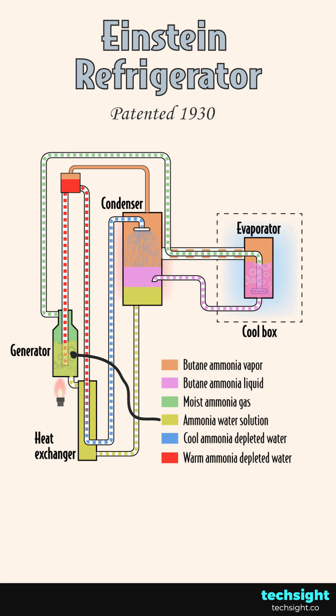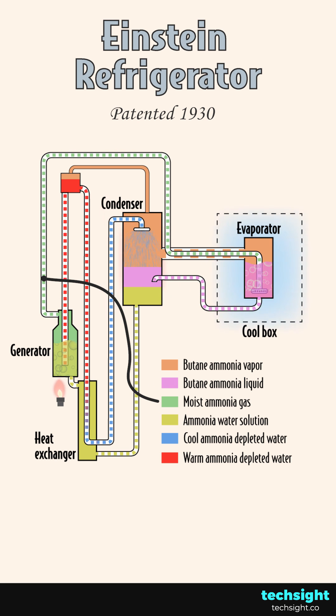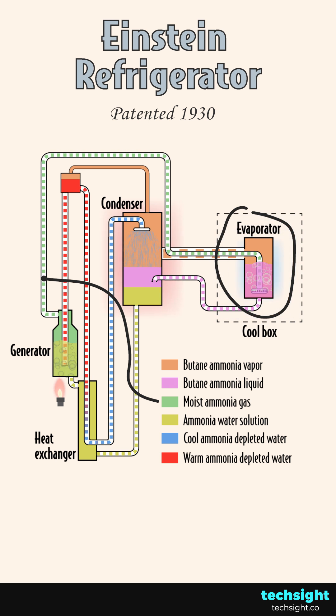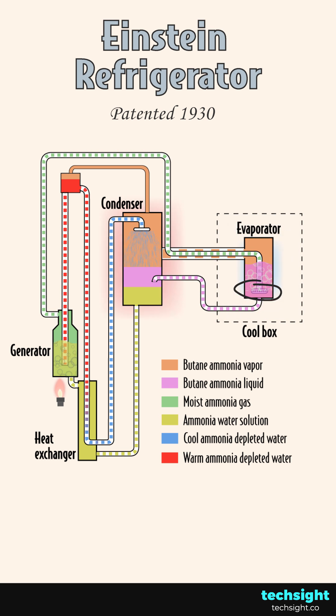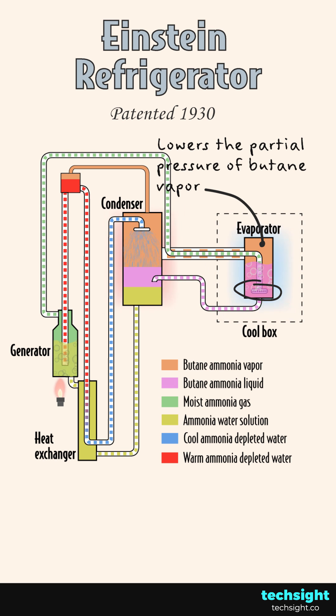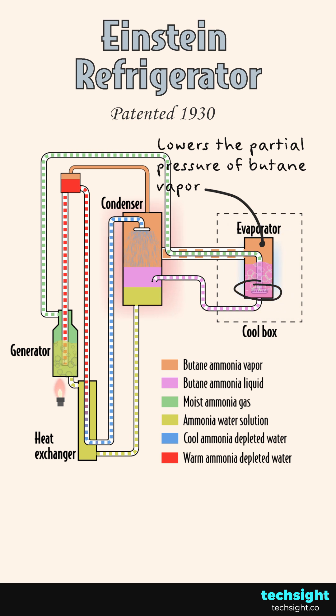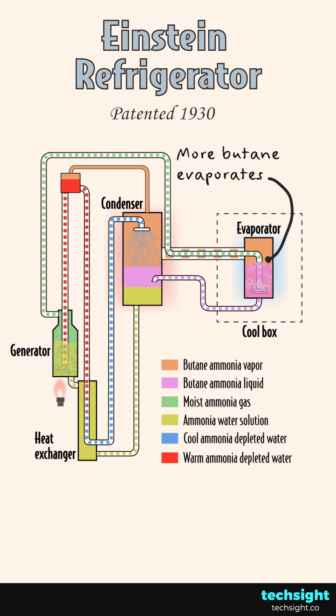Heat is applied to an ammonia water solution in the generator. Moist ammonia gas boils off and flows to the evaporator, which contains butane ammonia liquid and vapour. Bubbling the ammonia gas into the butane ammonia liquid lowers the partial pressure of the butane in the vapour mixture. Partial pressure is the pressure a gas will have when other gases it shares a container with are removed. In this case, the butane's partial pressure lowers enough to allow more butane to evaporate into gas.